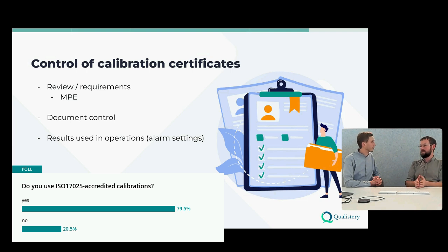One term at least that's really important to get in place is that there is no place in the GxP area where you can have non-traceable calibrations. They all need to be traceable to the International System of Units. Whether those are performed at an accredited or non-accredited calibration laboratory kind of does not matter, but they still have to be traceable. The part about reviewing is just easier.